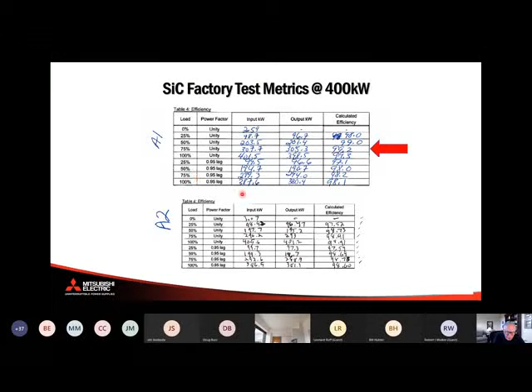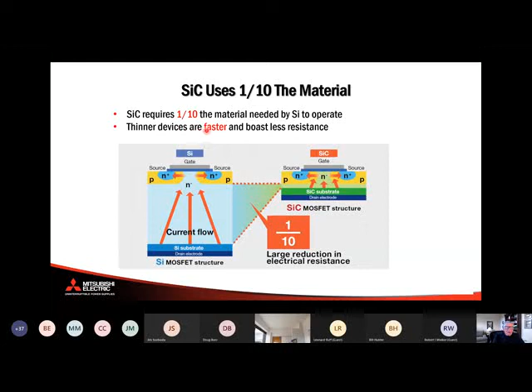Heat rejection. Because there's only 1/10 the material needed: silicon needs X amount, only 1/10 of that amount with silicon carbide. So thinner devices are faster and boast less resistance, less heat, etc. We're going to get, at 75% load, 50% less heat. At 100% load, 40% less heat. Your air conditioning bill goes down and the requirement for air conditioning devices goes down.